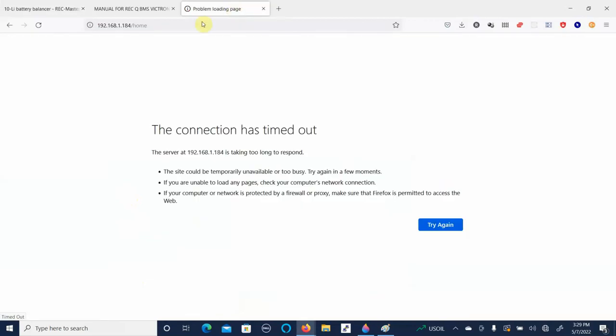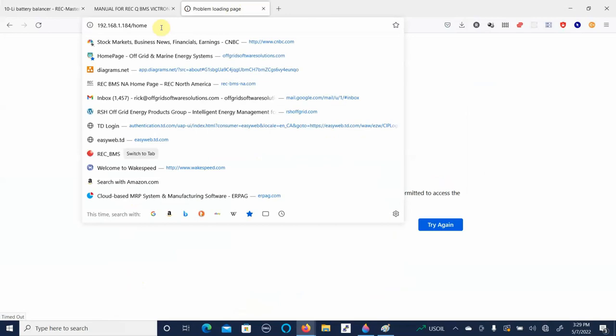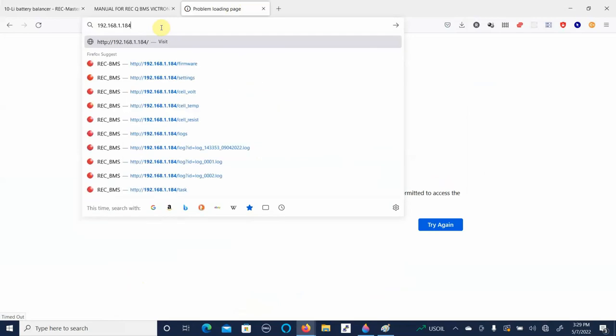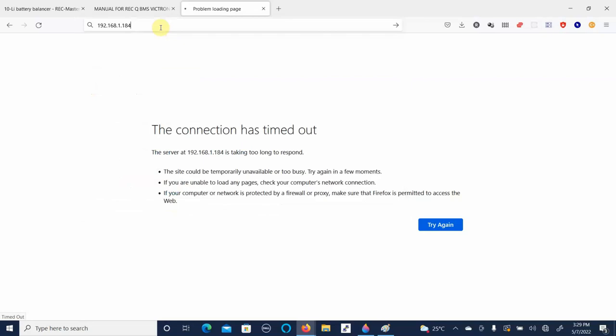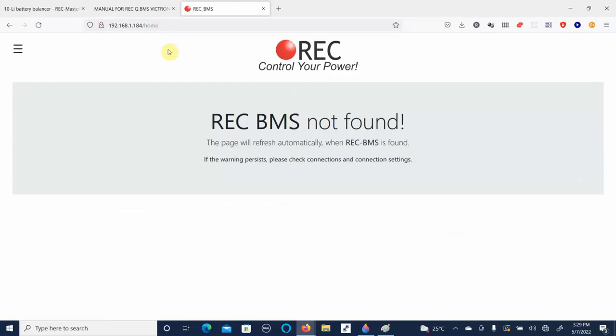Now its default is set to 192.168.1.184. So that's its physical address on the access point network. So we hit enter here, and we can see that we're connected to the Wi-Fi module, but not to the BMS. Now this is because we have to specify the BMS that we want to connect our Wi-Fi module to.